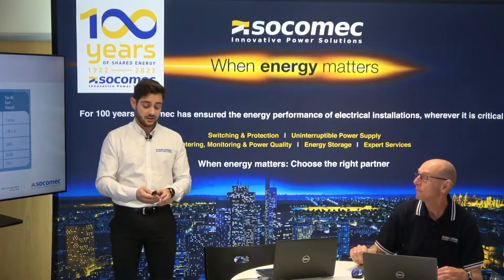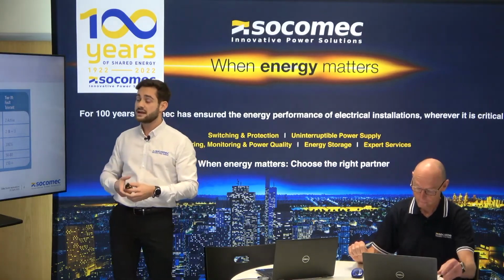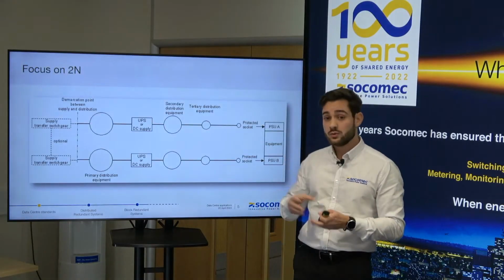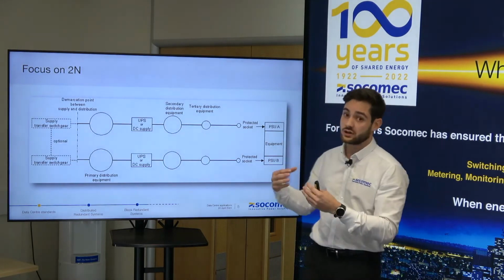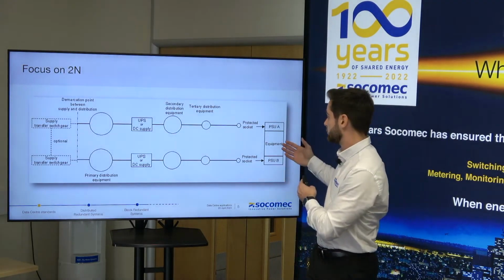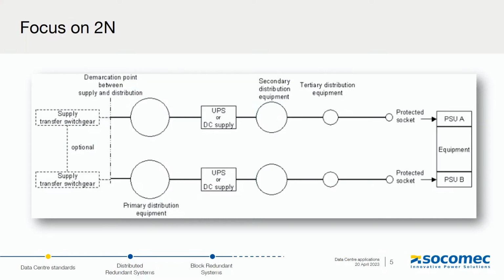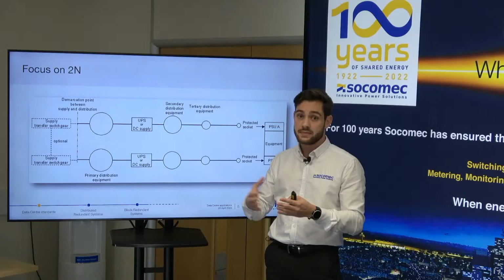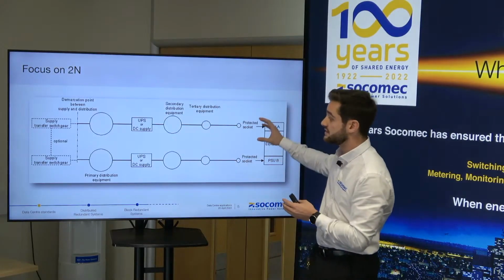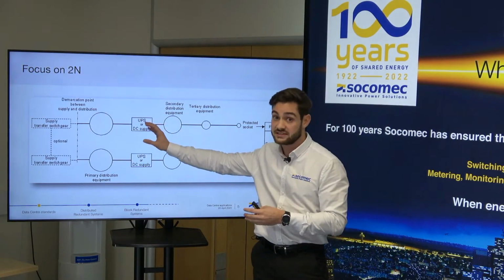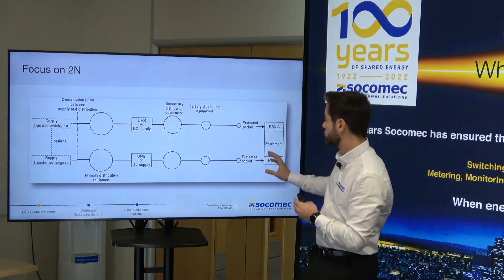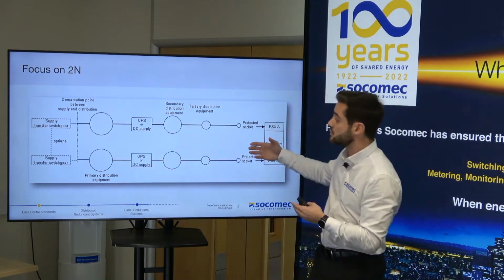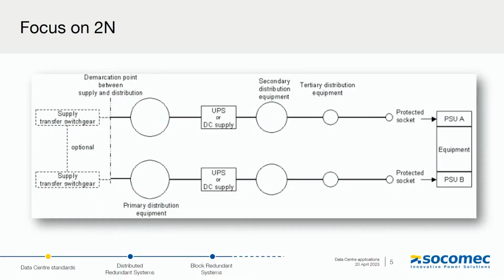Absolutely correct. So now we've understood the tier classification, let's focus on the 2N. What do we mean by 2N? As we said, when we have 2N, we've got two paths. So imagine you've got your equipment with, for example, dual corded servers. Each server would be fed via power supply units. On each leg, you would get 50% of the power. So imagine your equipment is a 3.6 megawatt load, for example. It means that your UPS system A will need to be rated at 3.6 megawatt, and exactly the same for UPS system B. In the event of a failure on one path, you can rely 100% on one system.